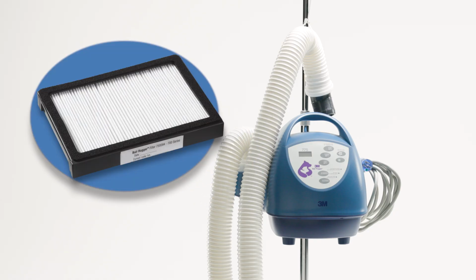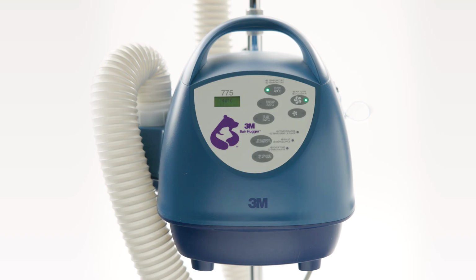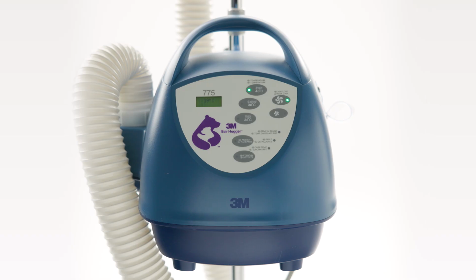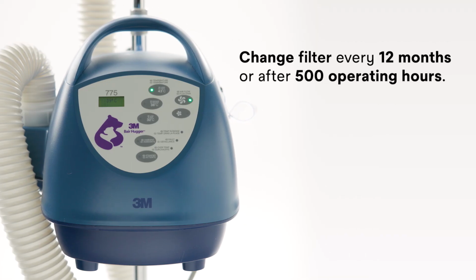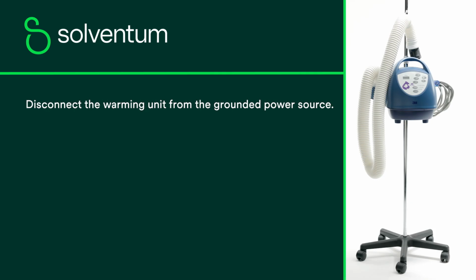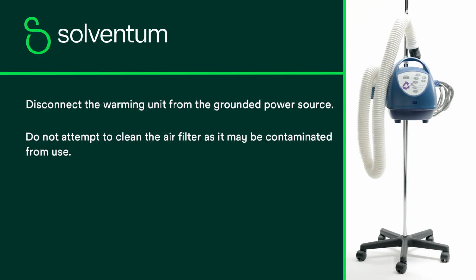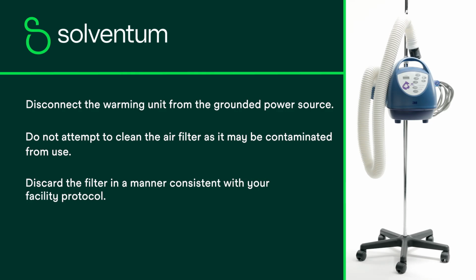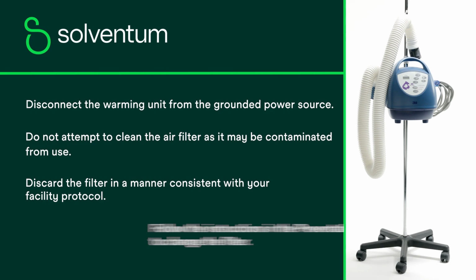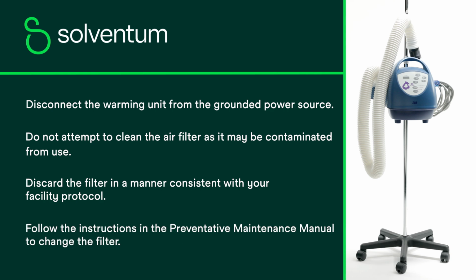The Bair Hugger Model 775 warming unit contains a MERV 14 rated filter. To keep your warming unit running at maximum efficiency, this filter should be changed every 12 months or after 500 operating hours. Disconnect the warming unit from the grounded power source. Do not attempt to clean the air filter as it may be contaminated from use. Discard the filter in a manner consistent with your facility protocol. Follow the instructions in the preventative maintenance manual to change the filter.